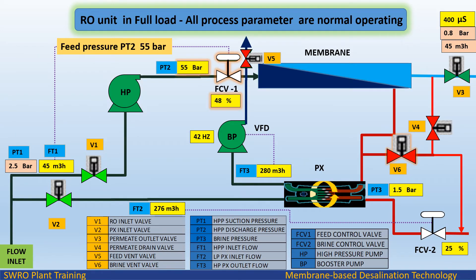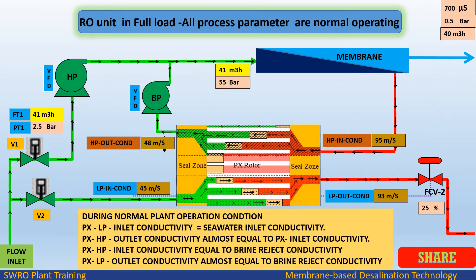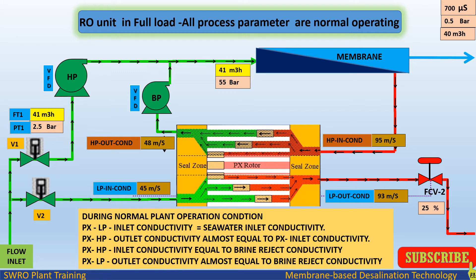RO Unit in Full Load Operation — all process parameters are at normal operating conditions. Feed pressure PT2 is 55 bar. During normal plant operation: PXLP Inlet Conductivity equals Seawater Inlet Conductivity; PXHP Outlet Conductivity almost equals PX Inlet Conductivity; PXHP Inlet Conductivity equals Brine Reject Conductivity; PXLP Outlet Conductivity almost equals Brine Reject Conductivity.